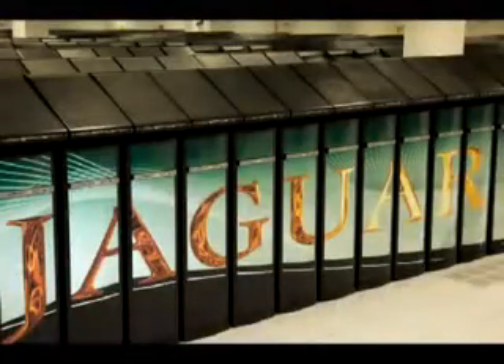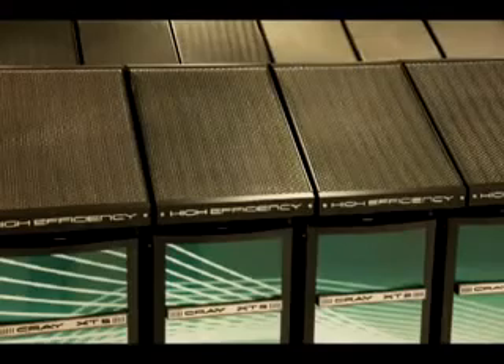Supercomputers consume massive amounts of energy. Jaguar is different. The ECOphlex technology uses phase change cooling — the hot air blows through an evaporator with a refrigerant in it, and it goes through a phase change transition where the liquid turns into a gas, and this is very, very efficient.